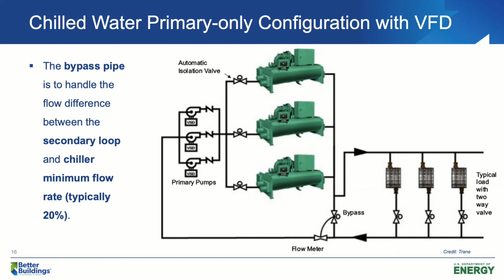In winter, or when the cooling loads are very low, the needed chill water flow is less than the minimum flow required by chillers. For that case, excessive flow will go through that small bypass line and go back to the end of the primary pumps. This way, we can make sure that our chillers will have enough chill water flow through the evaporators and they will work properly. Basically, we would like to make sure that the water flow rate through the evaporators will not drop below the minimum flow requirement.